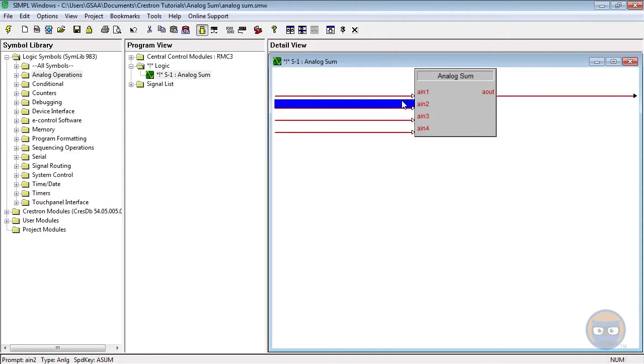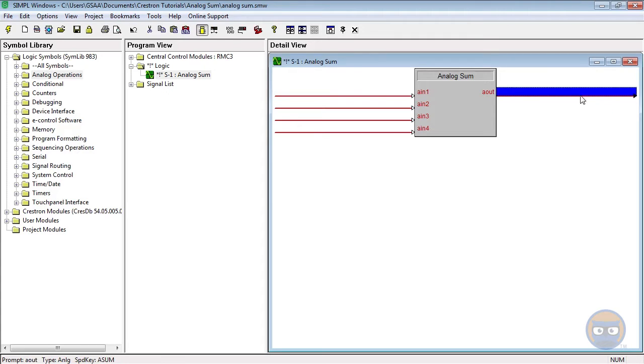The inputs can be signed or unsigned, but the output can either live in the range from 0 to 65,535 or from negative 32,768 to 32,767. You can't expect the output to have negative numbers and an output value of 40,000. This is simply a limitation of the numeric types offered in SIMPL.